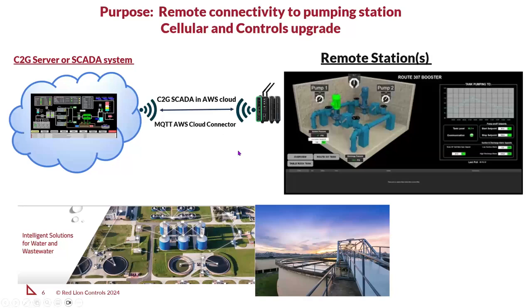So it doesn't matter whether you have local I/O at your pump station, Modbus TCP, or Ethernet products. We can convert that, package it down, and reduce the size via MQTT, and send it to anybody's SCADA or cloud system. With over 300 built-in protocols, Red Lion makes it easy to get information from anything to anywhere.